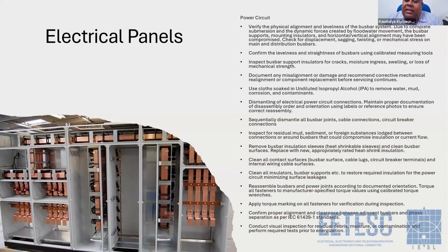Make sure the parts are leveled and well aligned, because the deformation of these bus bars will give you vibration, noises, and in the long term damage insulators, and can lead to a short circuit or an arc flash or ground faults. Therefore, make sure they are very well aligned and there are no deformations inside the switchboard.